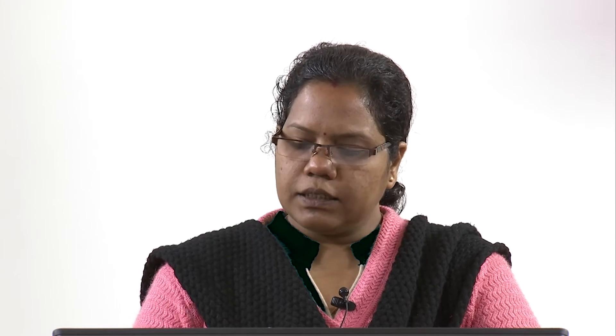After getting the phasors, we calculate the negative sequence component of the voltage: V2 = (1/3)(V_A + a²·V_B + a·V_C). Next, we also calculate I2, the negative sequence component of the current: I2 = (1/3)(I_A + a²·I_B + a·I_C).